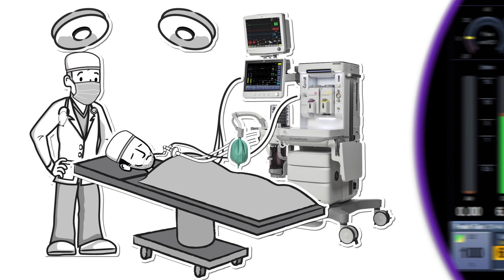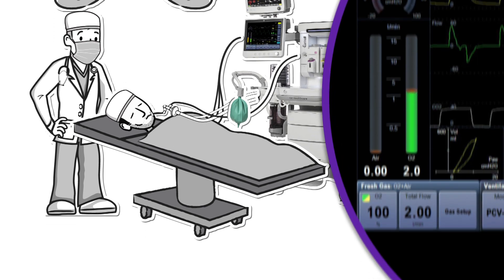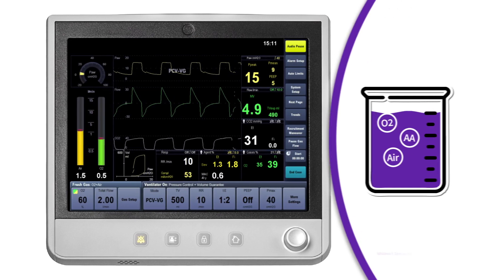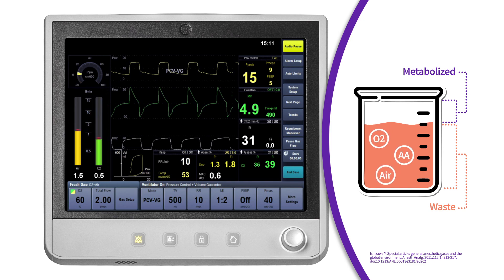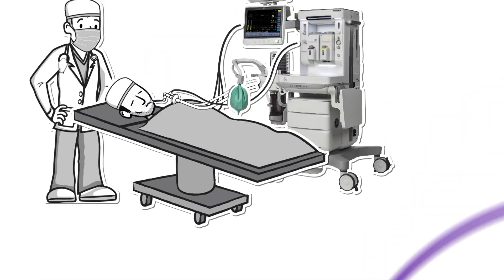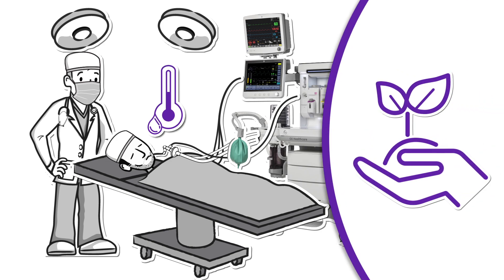Today, many anesthesia providers adjust their fresh gas flow rate to meet the patient's oxygen consumption. Typically, patients undergoing anesthesia only metabolize a small percentage of the anesthetic gas that an anesthesia machine delivers, causing flow rates to be higher than what the patient actually needs, creating waste. By lowering fresh gas flows, it helps to add heat and humidity to the patient breathing circuit to help maintain patient temperature and to reduce the environmental impact of anesthetic agent use.